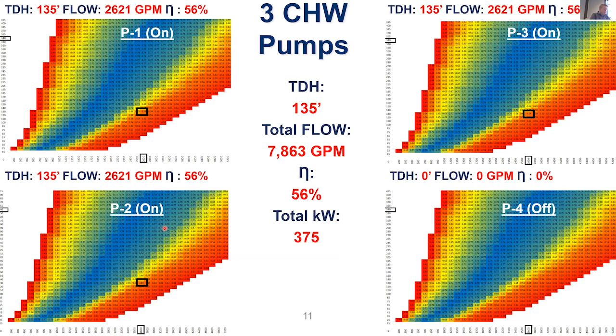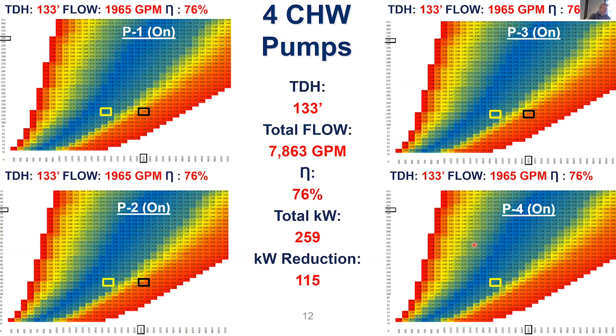The counterintuitive solution in this example is to turn on the 4th pump. So I went from 2,600 GPM per pump down to roughly 2,000 GPM per pump, or 1,965 GPM. Now I'm running 4 pumps. The pumps are running at or pretty close to their best efficiency point. It's at 76% efficiency, and the kW reduction is 115 kW.